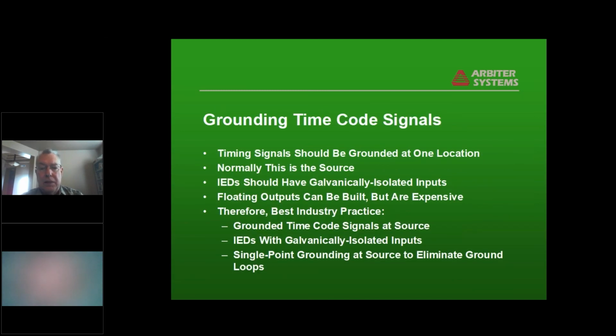We get questions from time to time about grounding. As with most signals that you're trying to transmit accurately, you need to have the signal grounded at only one location, normally at the source. Most IEDs should have, and most do have, galvanically isolated inputs using an opto-isolator or a digital isolator. You can build floating outputs, and we've done that, but they have to have an isolated power supply, so they cost a lot more than an output that's grounded at that point.